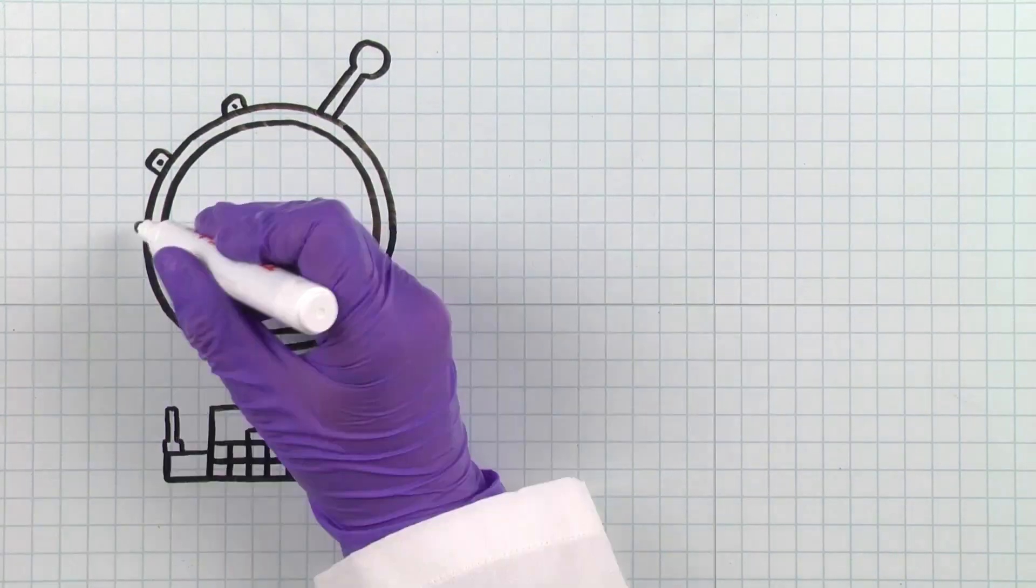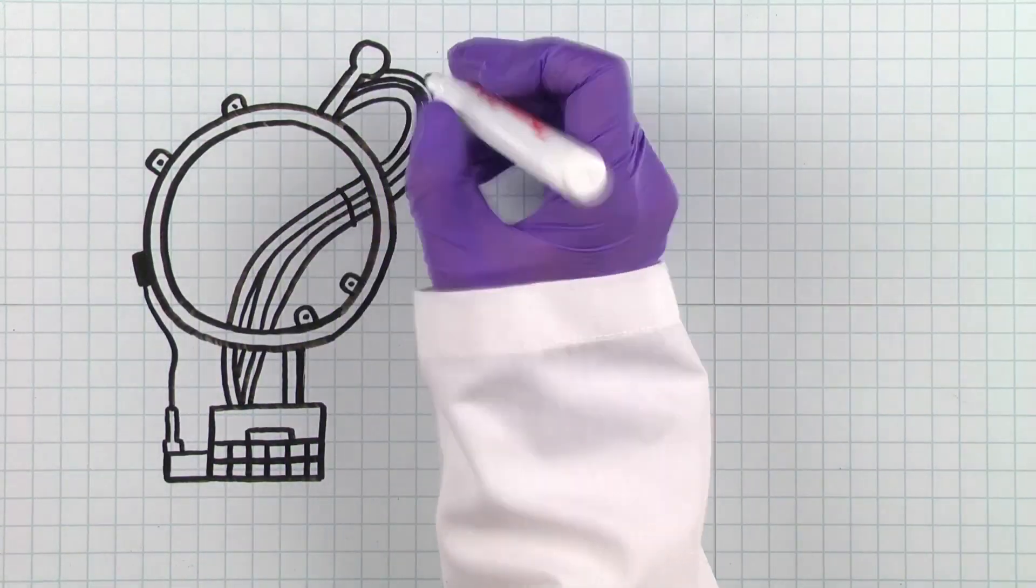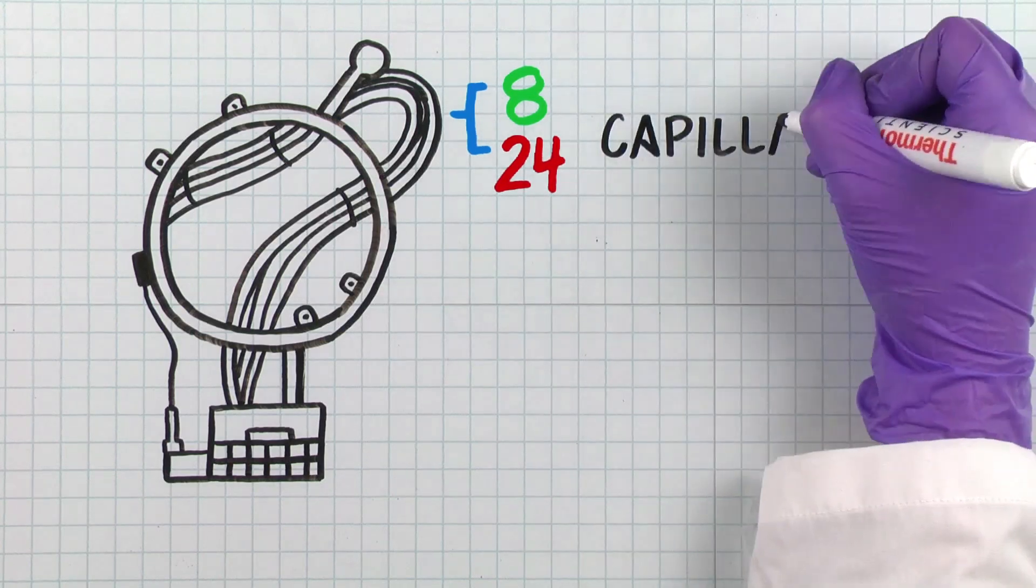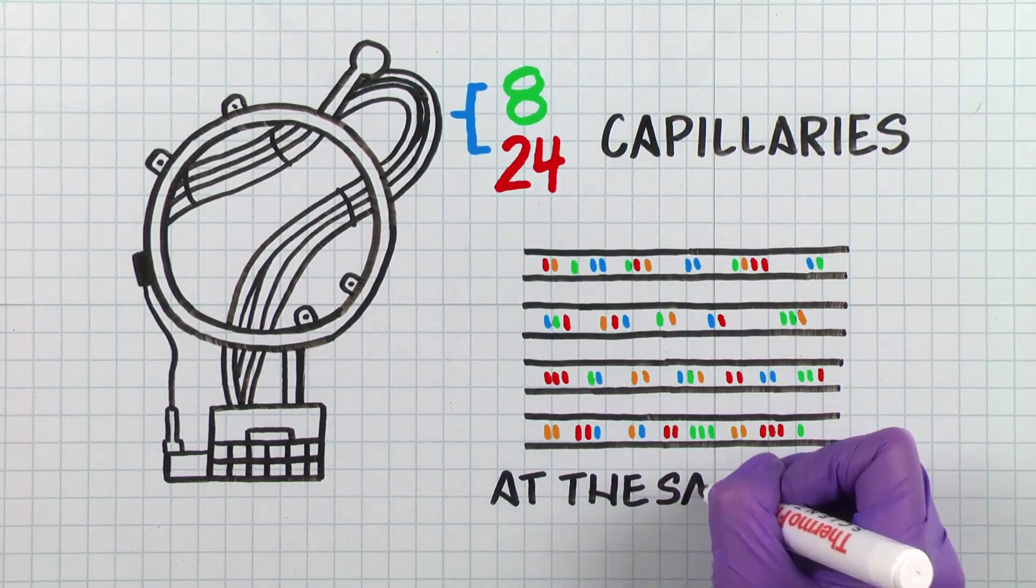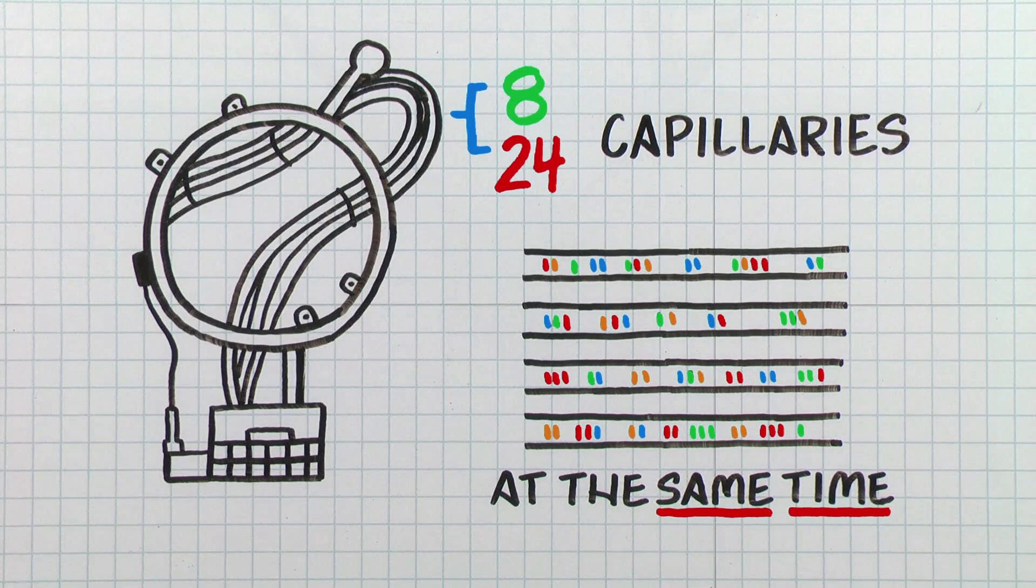Contrary to running one sample at a time sequentially, its capillary array consists of 8 and 24 capillaries, enabling all samples to run parallel to each other at the same time. These capillaries enable consistent results over long periods of time and across multiple capillaries.